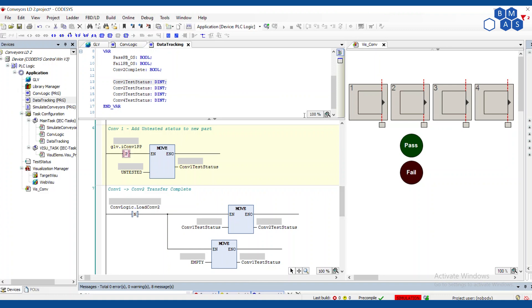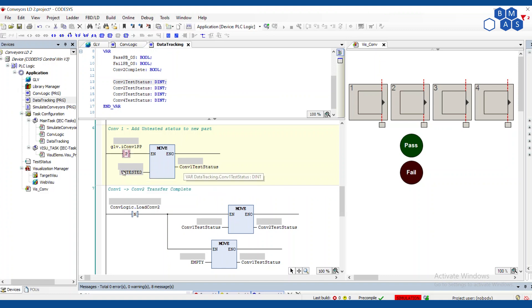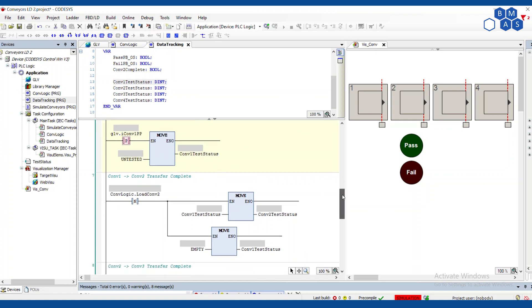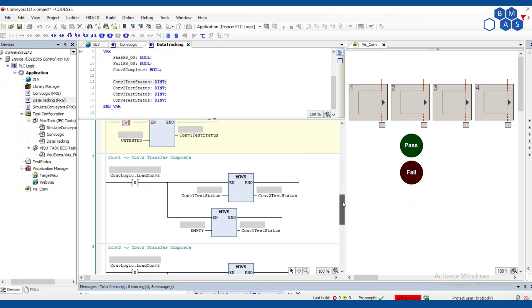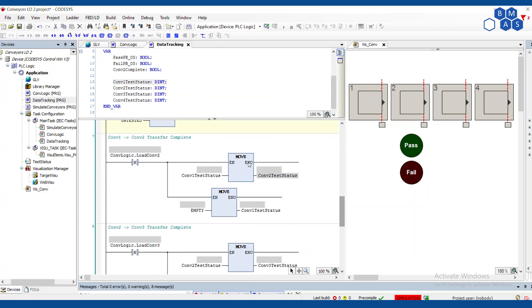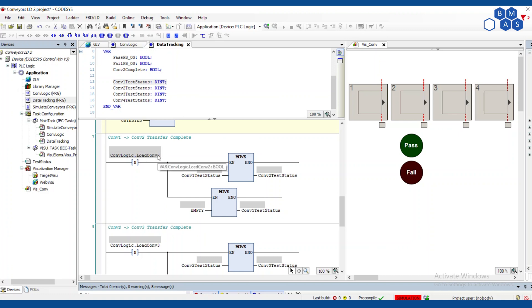The first and the last stations are obviously going to be a little different. They always are because it only has to worry about downstream and not upstream. In this case, I'm watching the sensor for conveyor one part present. When that has a rising edge, then we're going to move untested. Again, that's a constant into conveyor one test status. So you've seen that pop up here.